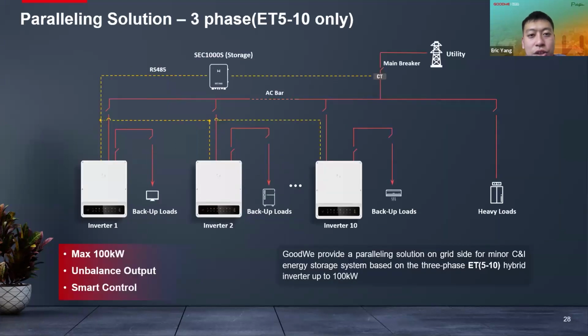And this is a parallel solution for three-phase. We have the ET 5 to 10 kilowatt. And in this solution, the backup loads of each inverter should be connected separately. That means we only parallel the on-grid side of the 10 pieces of ET 5 to 10 kilowatt. And in this solution, we need a control box. We call it SEC1000S, to communicate with these 10 pieces of ET 5 to 10 kilowatts. So it can realize a maximum of 100 kilowatts of hybrid inverter, 10 pieces of ET 10 kilowatts.